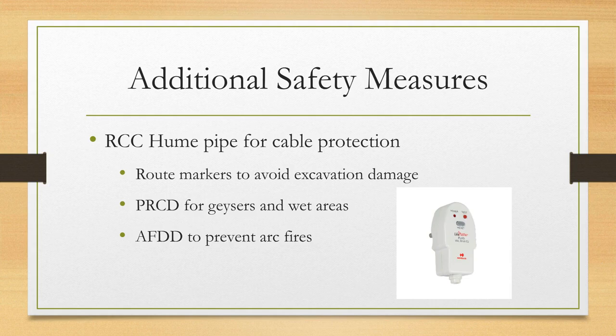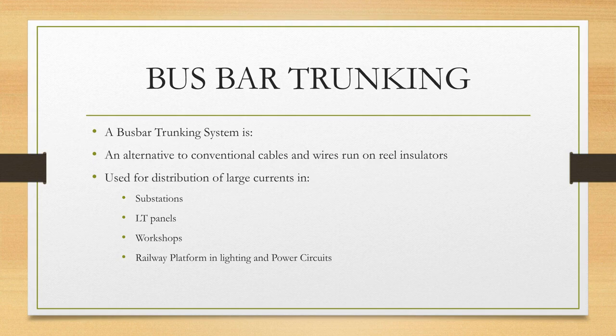Additional safety measures include using RCC Hume pipe for cable protection and route markers to prevent excavation damage. We also recommend PRCD for geysers and wet areas, and AFDDs to prevent arc fires. A busbar trunking system is an alternative to conventional cables used for distributing large currents in substations, LT panels, workshops, and railway platform lighting and power circuits.